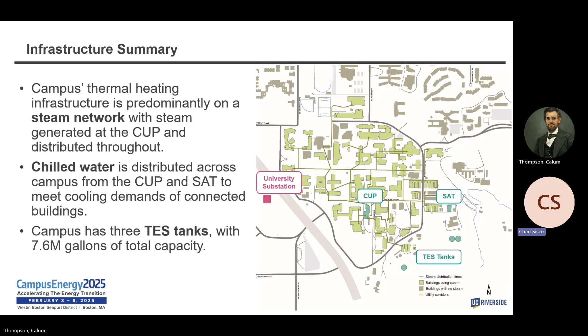Our infrastructure is centralized in three spots: the university substation on the west portion of campus that provides all of our electricity to the core campus, our steam plant located right in the center of campus, which we call CUP, Central Utility Plant, and our satellite plant, which only produces chilled water, located on the east side of campus near our TES tanks, which are in the hills on the south side of campus. Our tanks total a little over 7 million gallons of capacity.